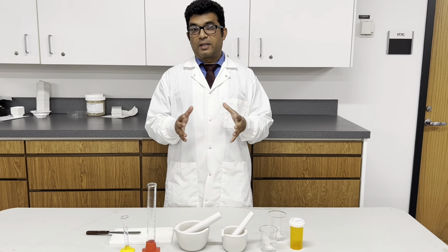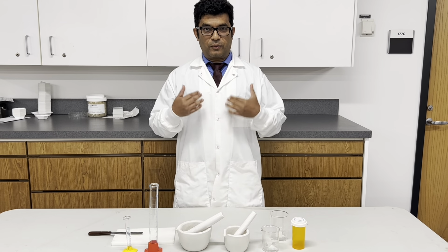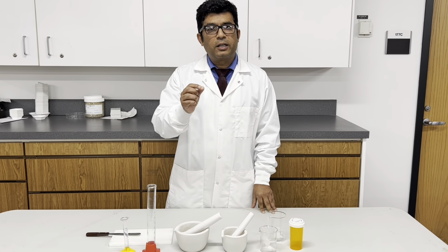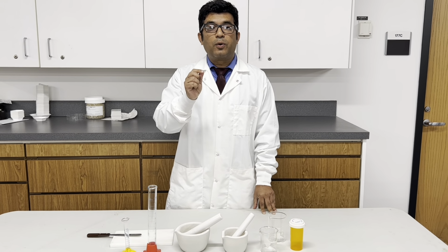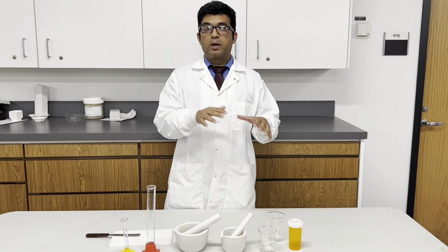Like you have a scale at home that you stand on and you know your own weight, like 50 kg or something. But if you put a piece of paper on there, you never see any weight. Why? Because it doesn't have enough weight to show in the reading. So this is the minimum accurately weighable quantity.